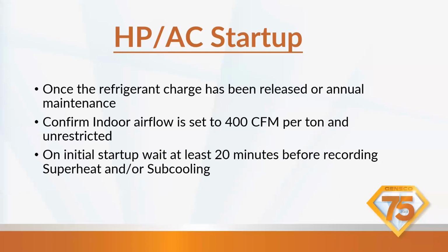Heat pump AC startup. Once the refrigerant charge has been released, or annual maintenance. So this is when a startup is, it could be the first time startup, or it could be you're going out there for an annual and you're making sure the system's running correctly. You're going to confirm indoor airflow is set to 400 CFM per ton and unrestricted. Unrestricted, I mean, if it's not new construction, or even if it's new construction, they could have a plugged filter. So make sure that the filter is clean and clear. Make sure that any plastic is removed off of a return air grill.